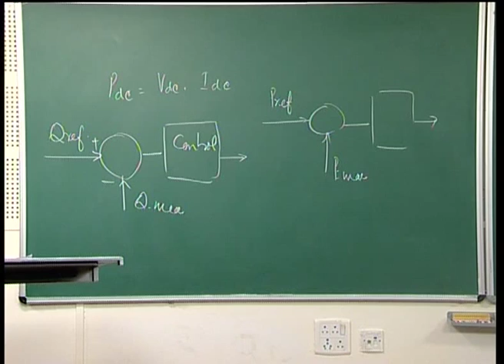In the whole HVDC light scheme there are 4 control loops: 2 loops for the rectifier and 2 loops for the inverter. At the inverter we are controlling the AC voltage as well as the DC, so these are called the AC voltage control loop and the DC voltage control loop. PI controllers are used for both the AC and DC control loops, using proportional integral control.